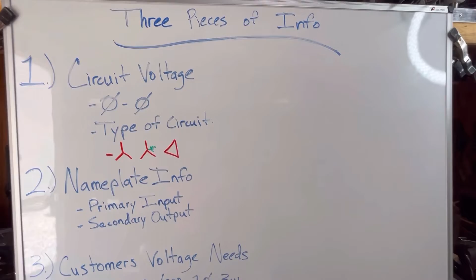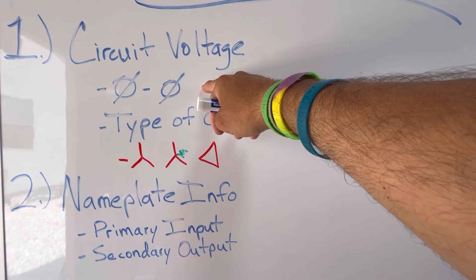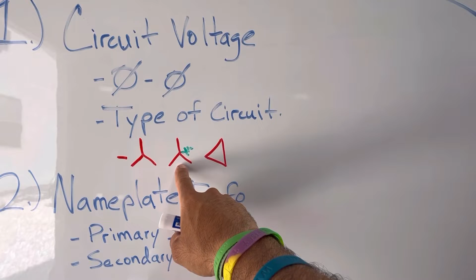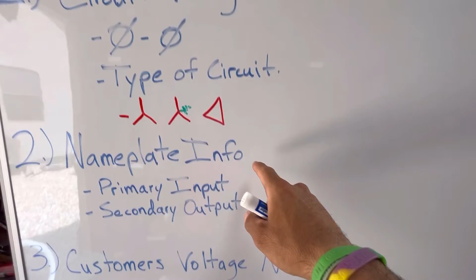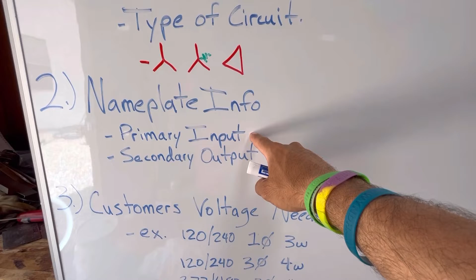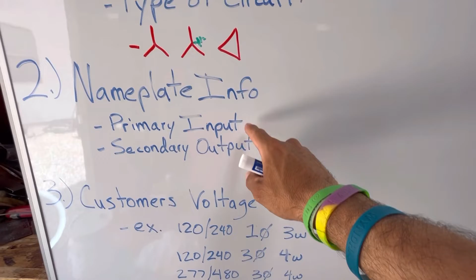All right, guys, so here we are. We've got our three pieces of information. We've got our circuit voltage, made up of the phase-to-phase potential of that circuit and the type of circuit that it is, whether it be a Y, a grounded Y, where the neutral is bonded to ground potential, or a delta. Next, we have our nameplate information, made up of our primary input, meaning what does the transformer need in voltage, and the secondary output, meaning if you give it whatever it needs, it's going to output whatever the number is on the secondary output.